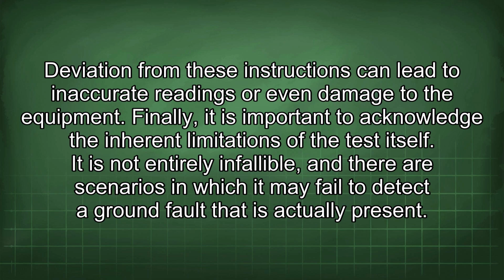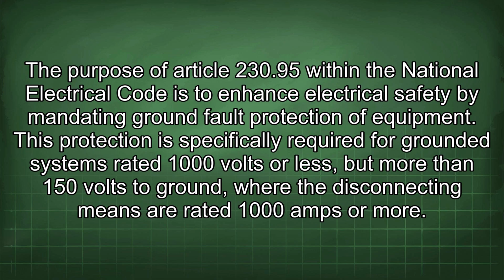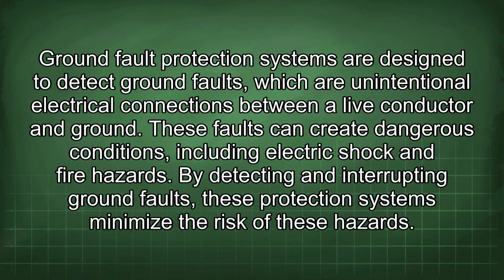The purpose of Article 230.95 within the National Electrical Code is to enhance electrical safety by mandating ground fault protection of equipment. This protection is specifically required for grounded systems rated 1000 volts or less, but more than 150 volts to ground, where the disconnecting means are rated 1000 amps or more. Ground fault protection systems are designed to detect ground faults, which are unintentional electrical connections between a live conductor and ground. These faults can create dangerous conditions, including electric shock and fire hazards. By detecting and interrupting ground faults, these protection systems minimize the risk of these hazards.